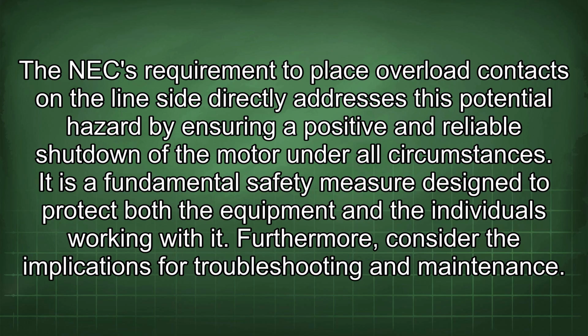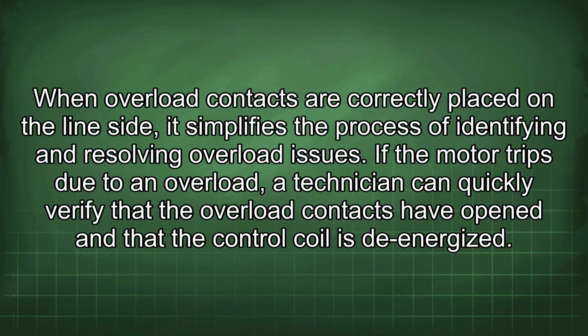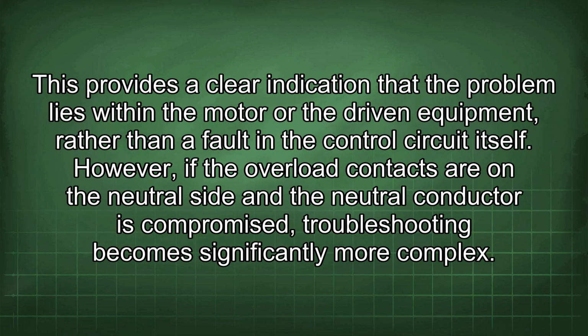Furthermore, consider the implications for troubleshooting and maintenance. When overload contacts are correctly placed on the line side, it simplifies the process of identifying and resolving overload issues. If the motor trips due to an overload, a technician can quickly verify that the overload contacts have opened and that the control coil is de-energized. This provides a clear indication that the problem lies within the motor or the driven equipment rather than a fault in the control circuit itself.